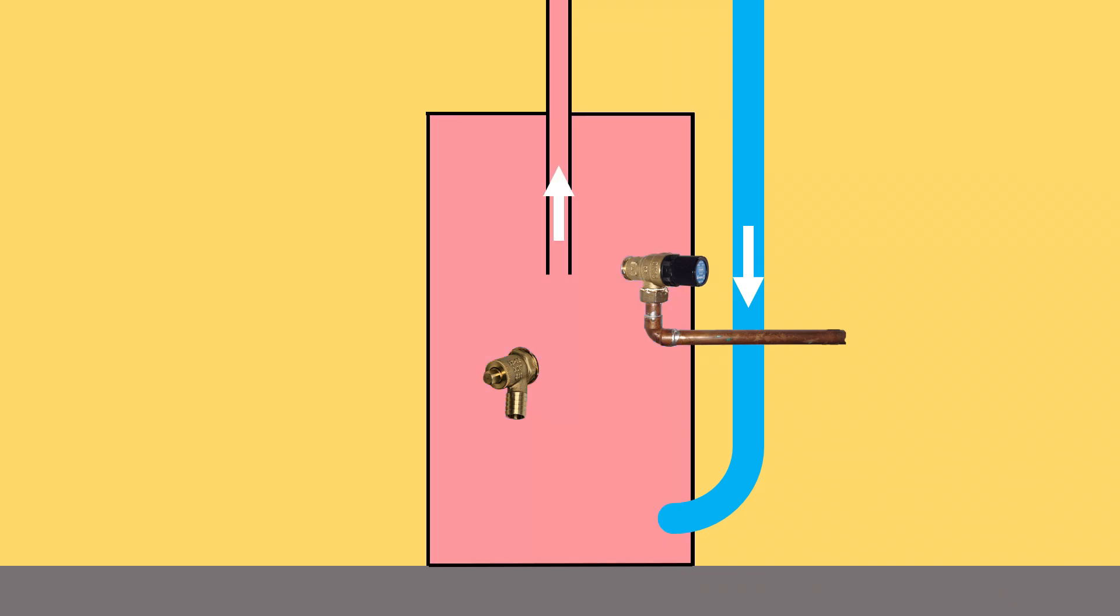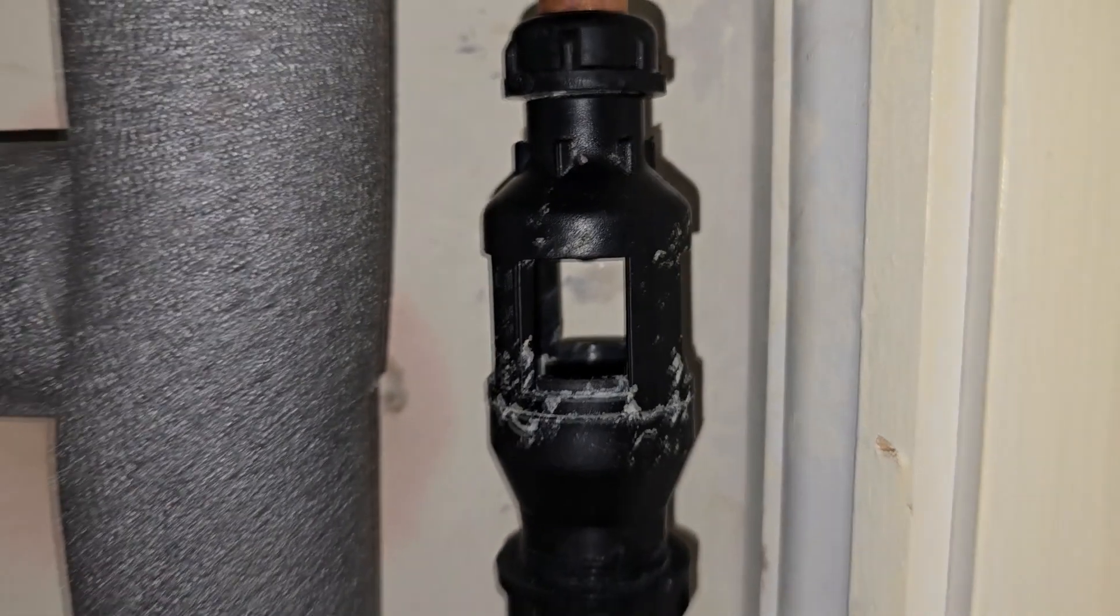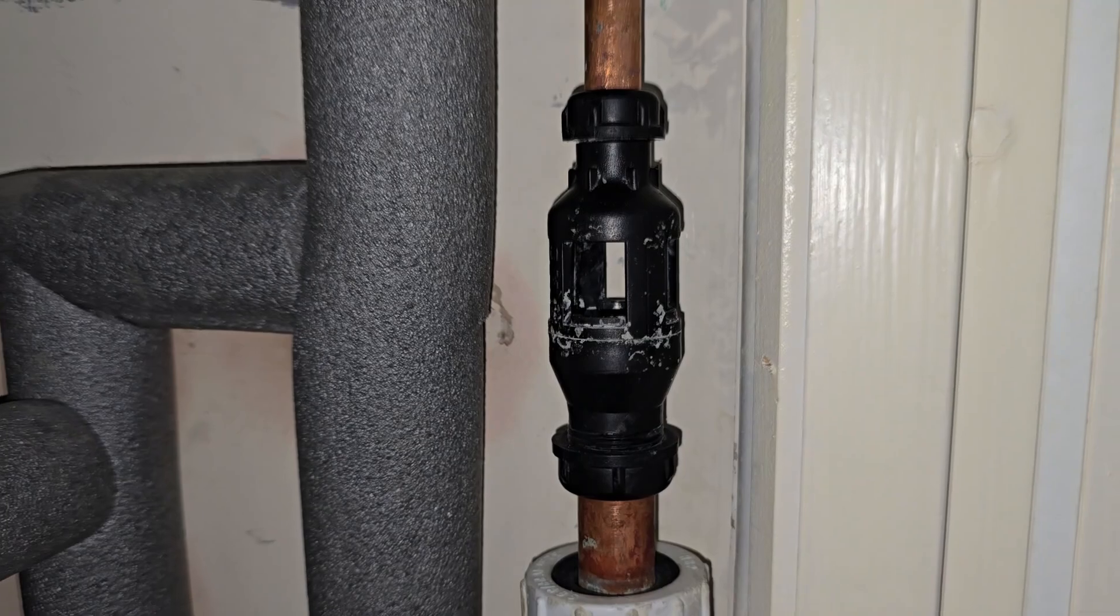Over long periods of use, the air trapped in an unvented cylinder dissolves into the water. As the water heats up, it expands and escapes through pressure relief valves.